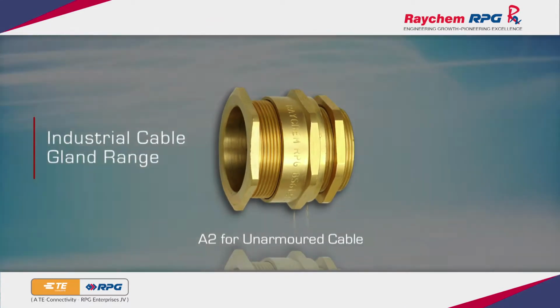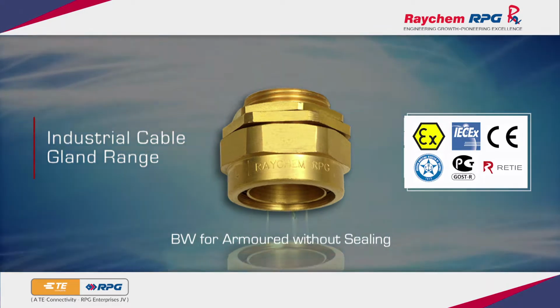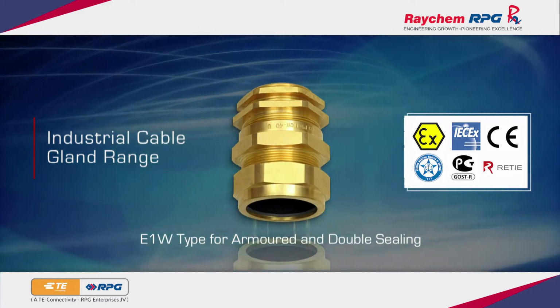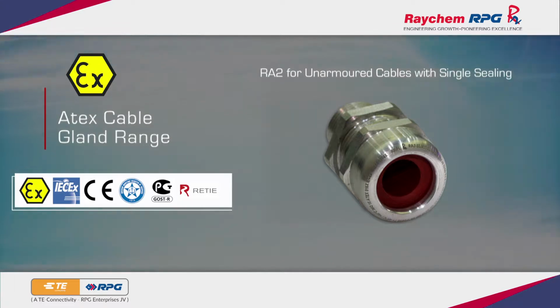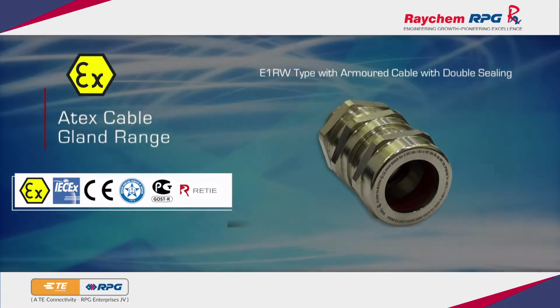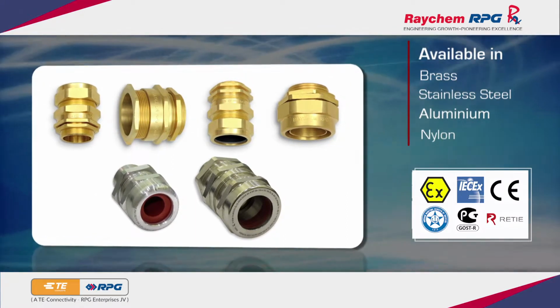The industrial glands range consists of A2 gland for unarmored cable, BW gland for armored cable without sealing, CW gland for armored cable with sealing, and E1W gland for armored cable with double sealing. The ATEX range consists of RA2 gland for unarmored cables with single sealing and E1RW gland for armored cables with double sealing. Glands are available in brass, stainless steel, aluminium and nylon.